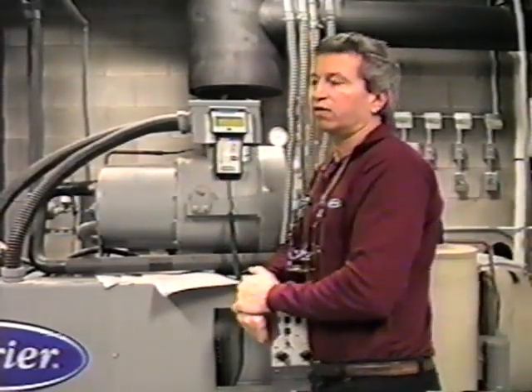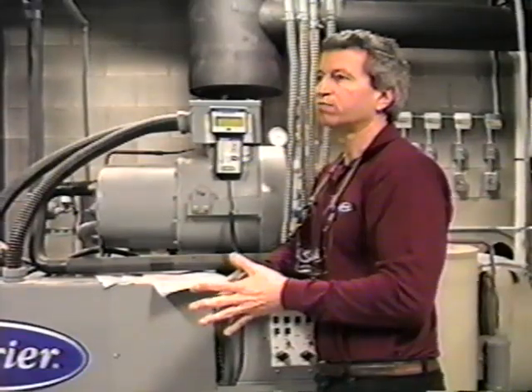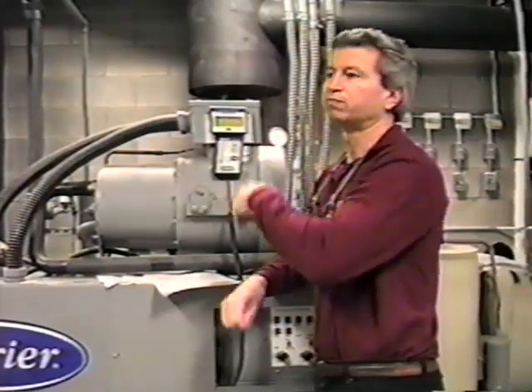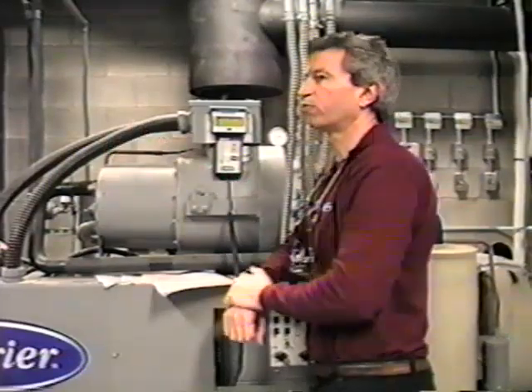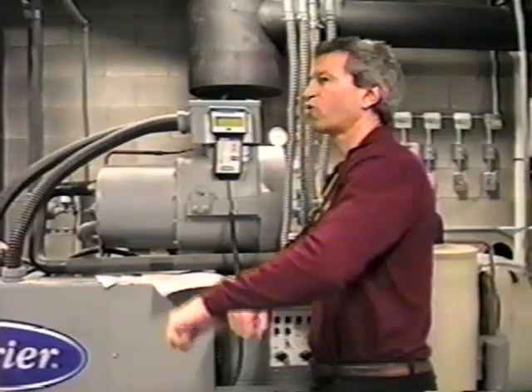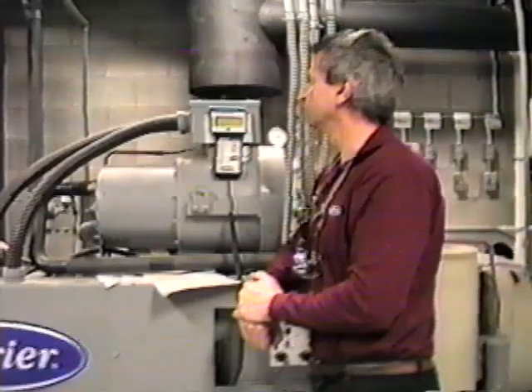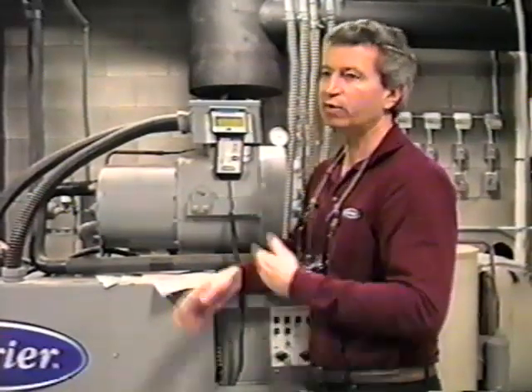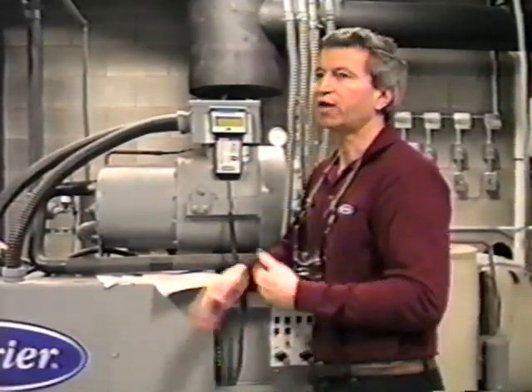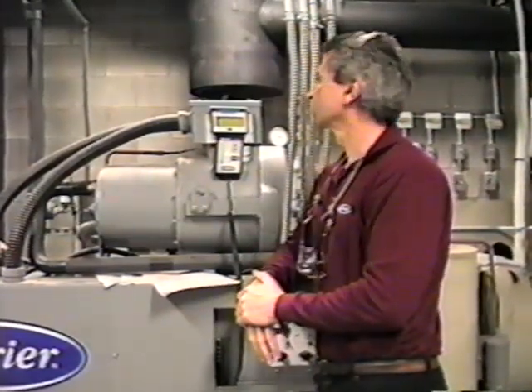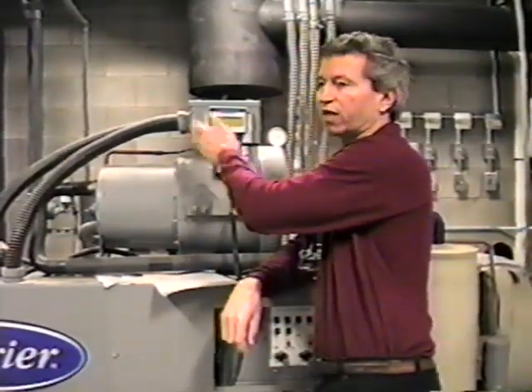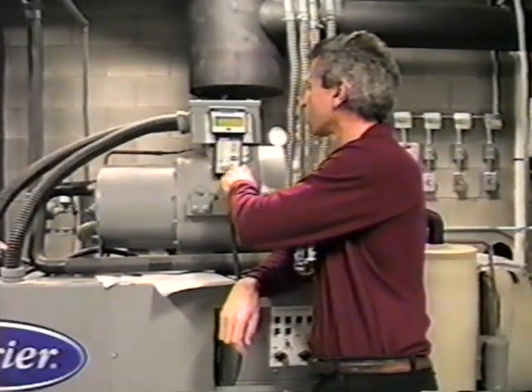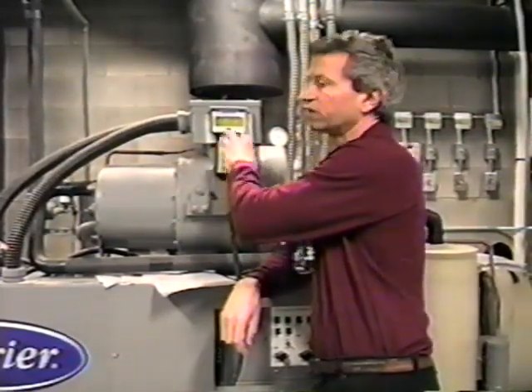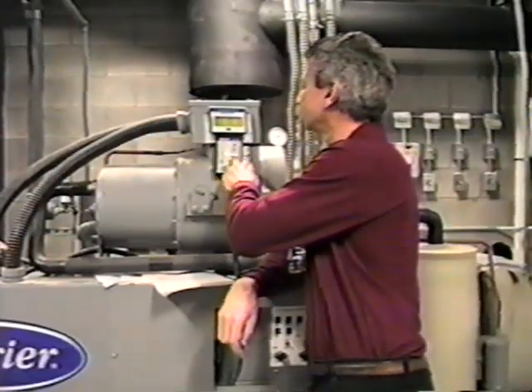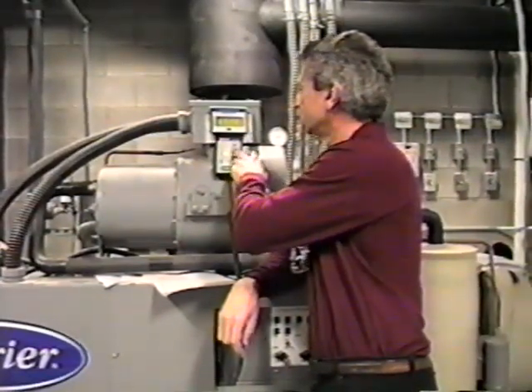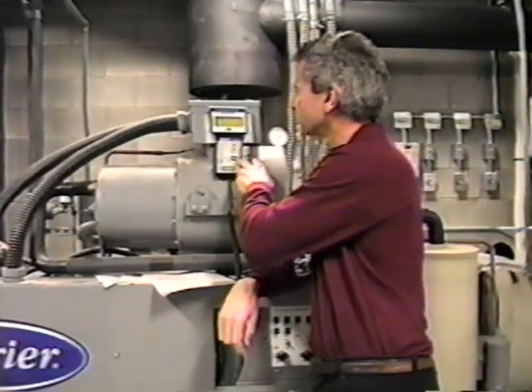Ramp load limited. We do have ramp loading at initial startup so that it doesn't just quickly load right up, run flat out with 2 compressors up, fully running, pull the load down real quick and then have to shut back down. So we have ramp loading. It's going to pull down so many degrees per minute at that rate until it gets down to temperature. So you may see that at any given time, primarily right after startup. And there's a number of them. And again, these are all listed in your manual. Rather than go through all of them, just make you aware that they're there.